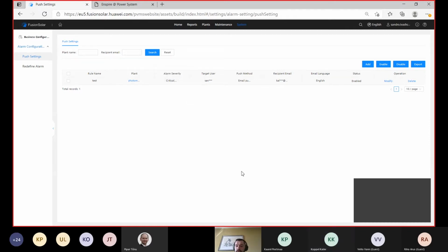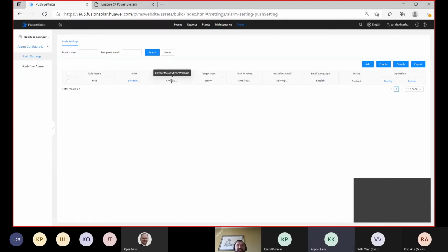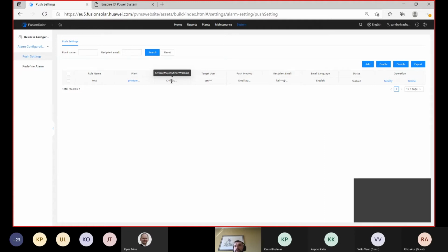If you have some question, you can text or ask me in the chat. What kind of alarms can we choose? What do you recommend to choose? It's up to you. I always recommend to choose critical and major alarms. You definitely need them. If you lose the grid or something happens with the inverter or the module, you will always get these critical or major alarms. Also, the minor is usually when you lose the communication with the inverter. It can be only for 5 minutes, for example, and you don't need to know about it.